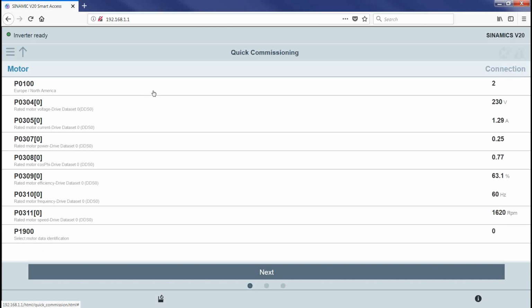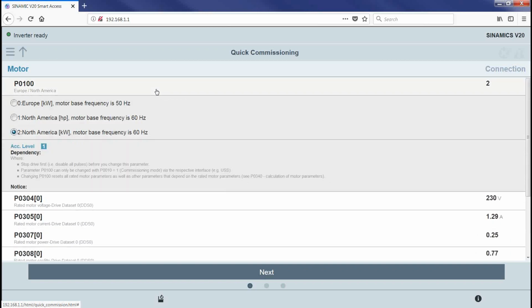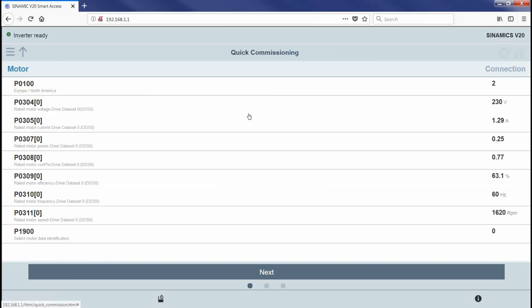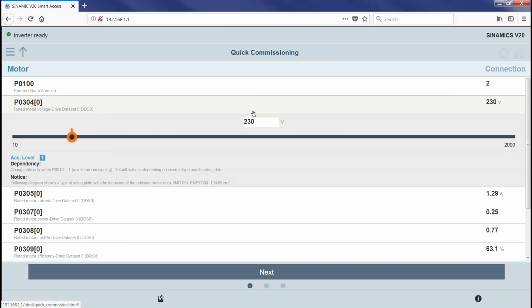So again, here's our parameters in the V20. They're going to vary slightly from what the G120 is. It's a little more capable drive, so there's more choices. For this, I've got a Siemens motor on my demo, so I'm just going to use North American, but I'm going to keep it in kilowatts because that's going to match up better with what I see on my nameplate. Rated motor voltage is 230 volts.